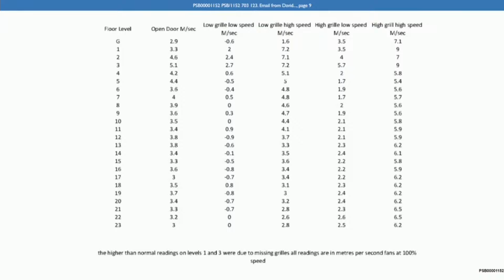Sorry, yes, one final question on this airflow across doors. Did you ever take any airflow readings across any other door other than the stair door at any stage? No, but when we were doing a certain test, which is the one where we were testing a fire on a floor, then activate the main fireman's override switch, and then we'd activate the key switch on that level. Yes, the yellow key switch. That would open the dampers on that level. The fans would start up. We'd open the door, make sure that the fans ramped up to full speed. We'd then close the door, make sure the fans dropped down.